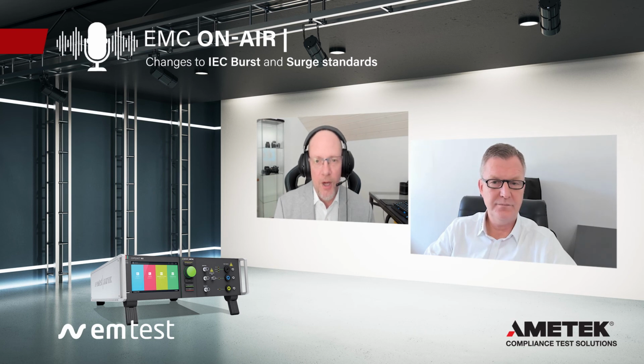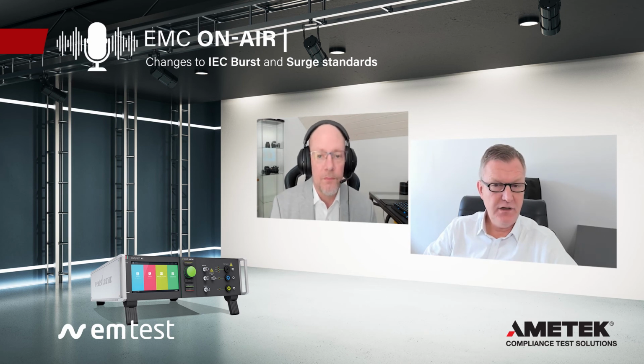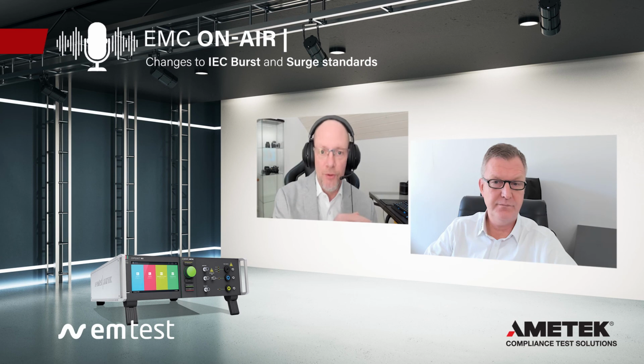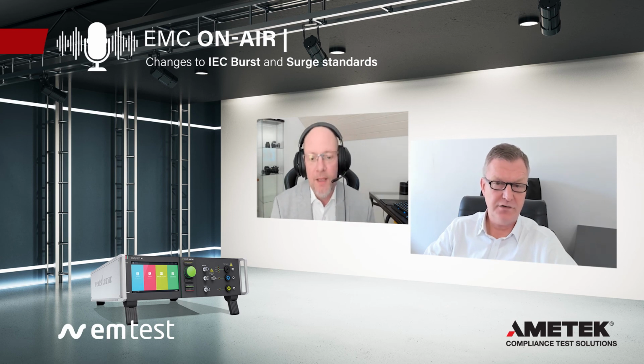So you talked about revision 2 quite a lot. Are there cases where people might or should still use revision 2 of the standard? Yes, there are. That's a good question, Tim. We have cases where customers still need to use edition 2, because if they have a product standard with a dated link to the previous standard, then they have to use an edition 2 generator. And it is possible that we deliver a device with 2 types of different calibration certificates, one according to edition 2 and one for edition 3. Interesting. So okay, now it all makes sense. So if the product standard still refers to the old standard, you use the old standard. That makes it clear now.